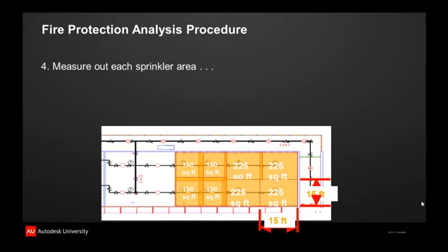And then the next four neighbors to the left of that are not as spaced as far apart, only 10 feet in one direction and 15 in the other, so that those are required to get enough water for 150 square feet each.